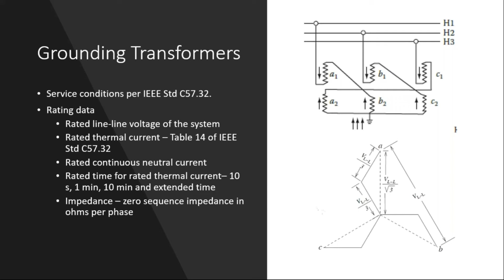In this case, for example, if we take a grounding transformer with zigzag windings, you have 6 windings in total, and the windings are connected from one leg to the other leg. So the connection forms in a way that you see in the vector diagram here. We can have this kind of relationship here. And what happens is that when you have a single line to ground fault, say in phase H3, the current flows from the neutral, and it flows in the windings A2, B2, and C2. And from B2, it goes to A1.